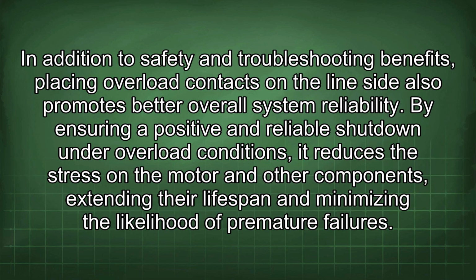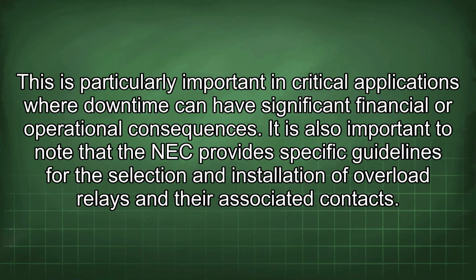In addition to safety and troubleshooting benefits, placing overload contacts on the line side also promotes better overall system reliability. By ensuring a positive and reliable shutdown under overload conditions, it reduces the stress on the motor and other components, extending the lifespan and minimizing the likelihood of premature failures. This is particularly important in critical applications where downtime can have significant financial or operational consequences.